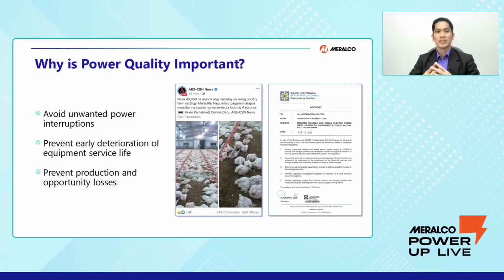So why is power quality important? We have to avoid unwanted power interruptions to prevent early deterioration of our equipment's service life, as well as to prevent production and opportunity losses. In 2020, there was news on social media wherein 43,000 chickens died at a poultry farm in the Laguna area because of loss of power. This came after a pre-arranged interruption conducted by Meralco. However, the poultry farm was unable to switch their power supply from Meralco to their generating set. Thus, for more than 4 hours without power, the lack of ventilation affected the chickens. It resulted in production and opportunity losses.